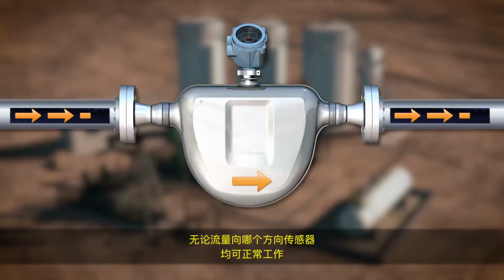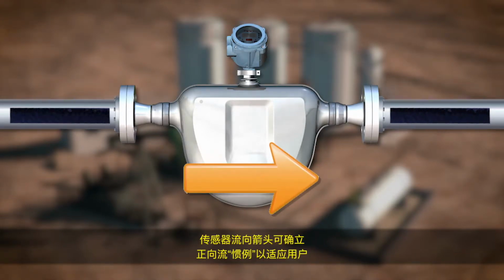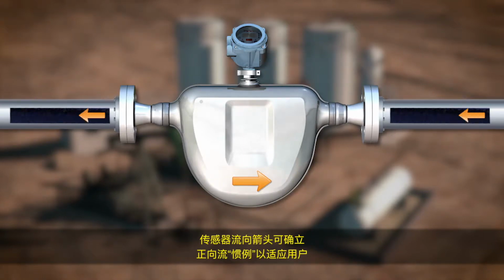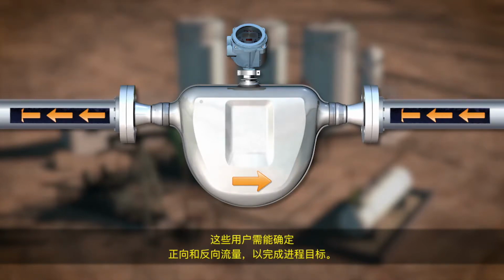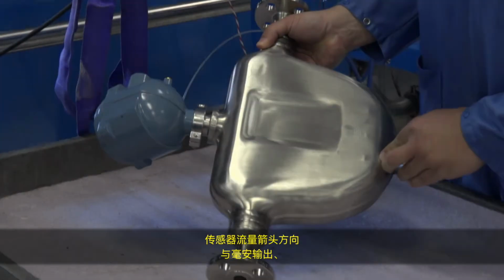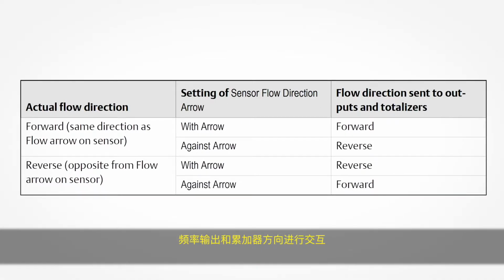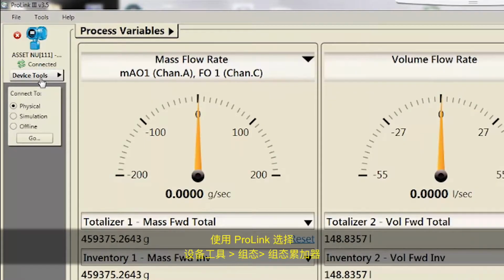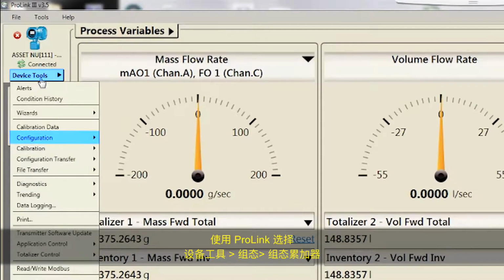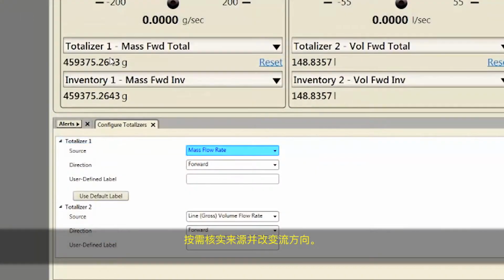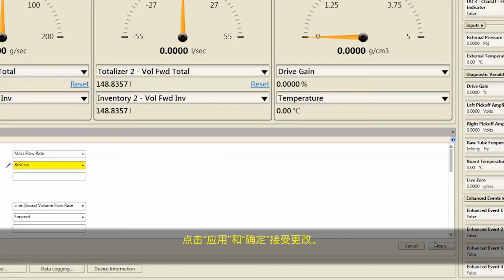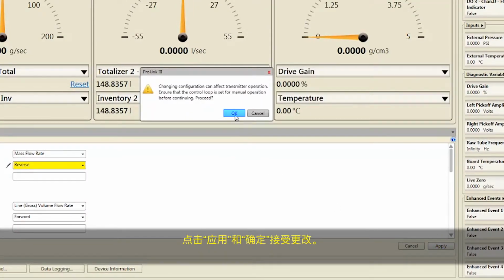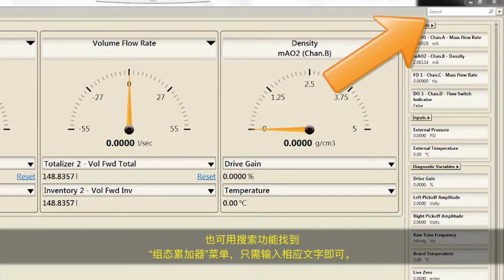The sensor works equally well with flow in either direction. The sensor flow direction arrow establishes a convention of forward flow to accommodate customers who need to be able to define forward and reverse flow for process purposes. The sensor flow direction arrow interacts with milliamp outputs, frequency outputs, and totalizer direction to control how flow is reported by the outputs and accumulated by the totalizers and inventories. Using ProLink, select Device Tools, Configuration, Configure Totalizers. Verify the source and change flow direction as needed. Click Apply and OK to accept all the changes. The search function can also be used to find the Configure Totalizers menu by typing Configure Totalizers.